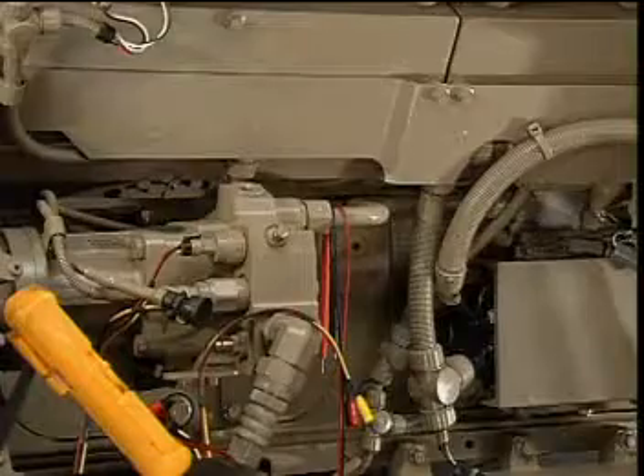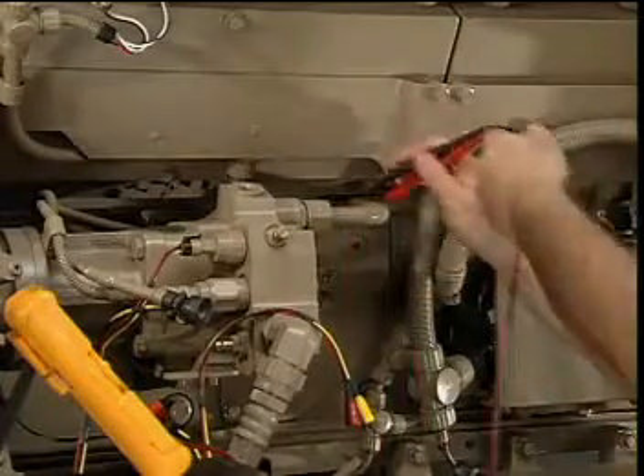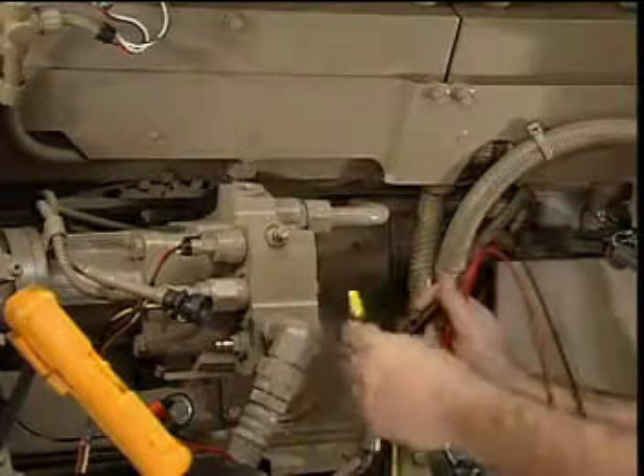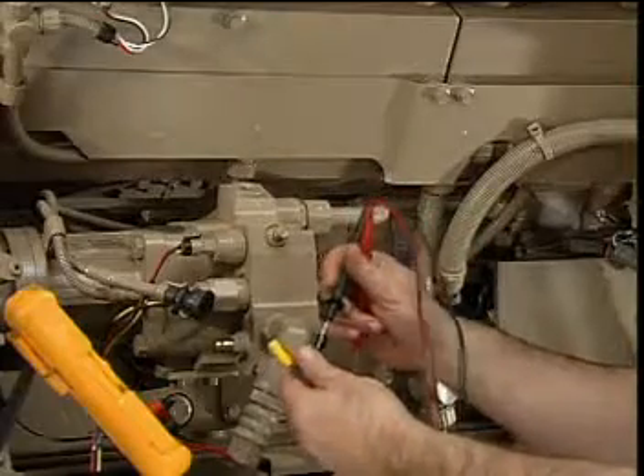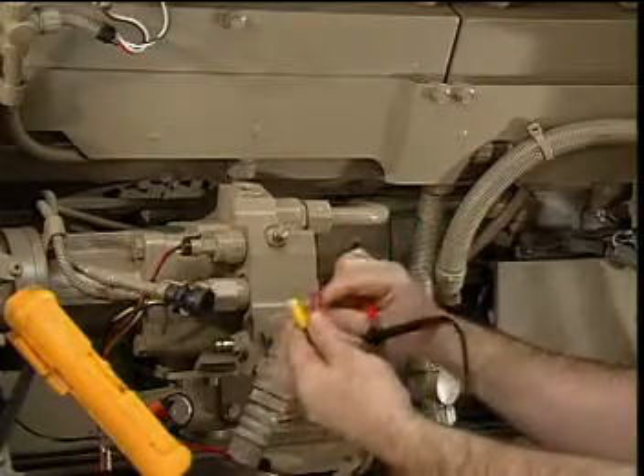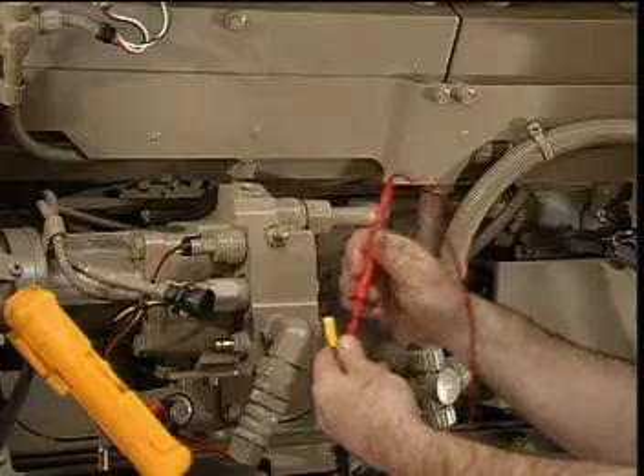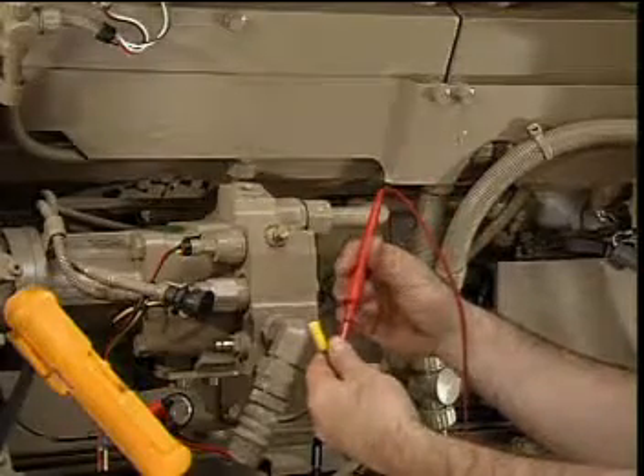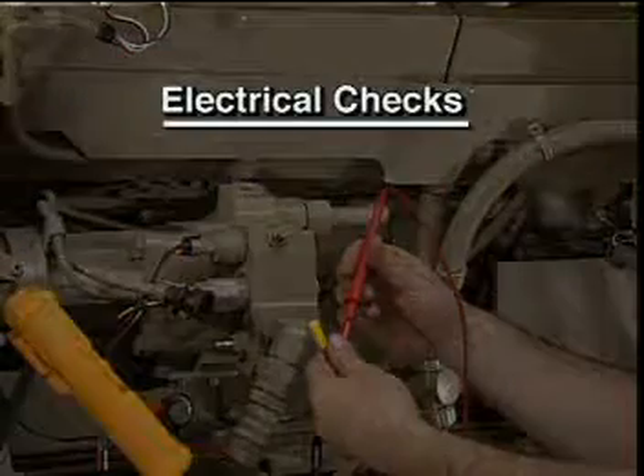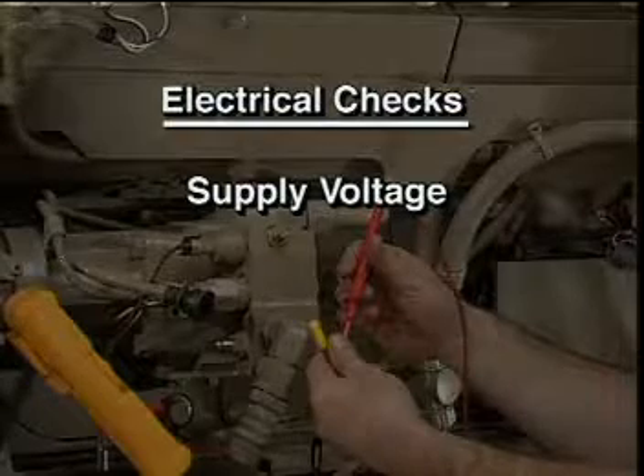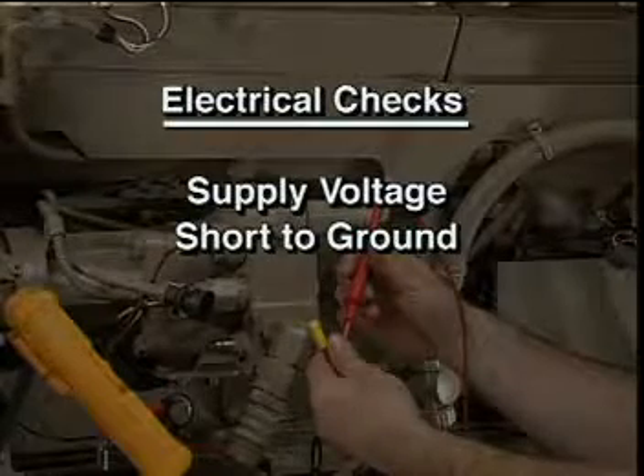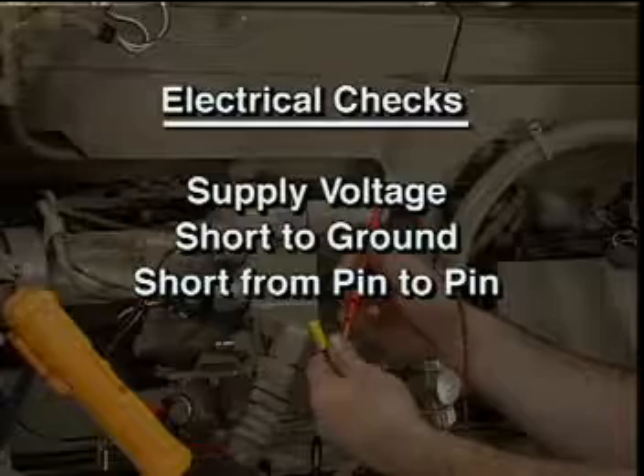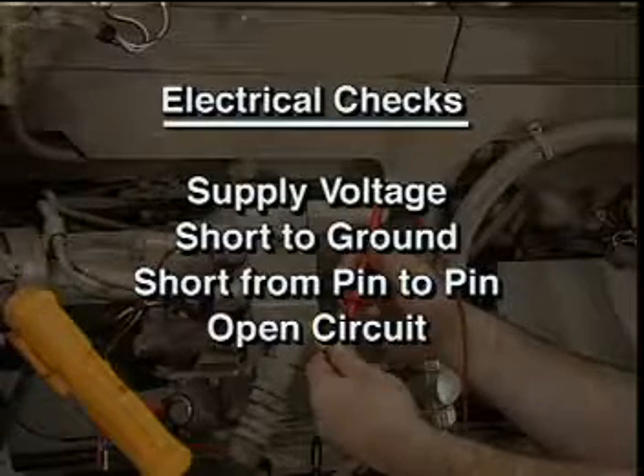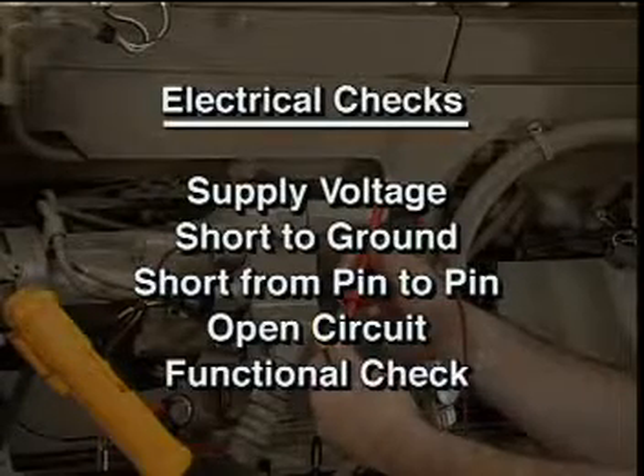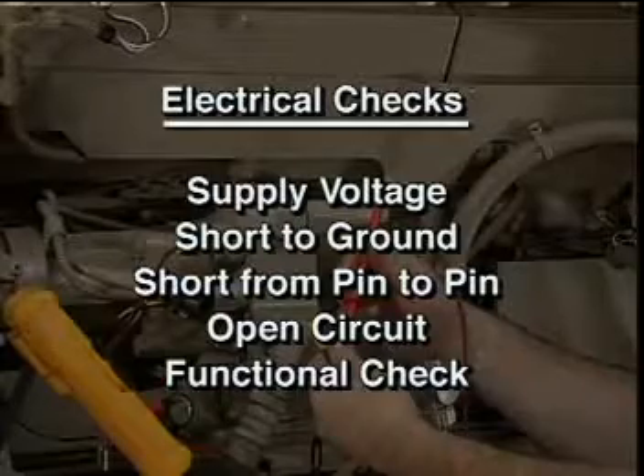When troubleshooting electrical components, similar types of procedures are normally followed. Although each of these steps cannot always be performed on each circuit, when they can be checked, these procedures verify if the circuit is performing properly. Check for the desired supply voltage to the component. Check for a short to ground. Check for a short from pin to pin in the connector. Check for an open circuit. And when possible, perform a function check of the component.